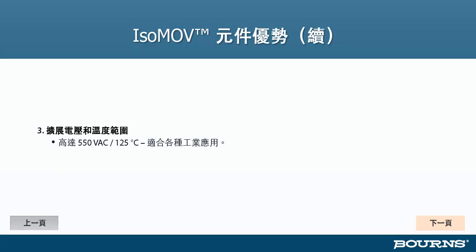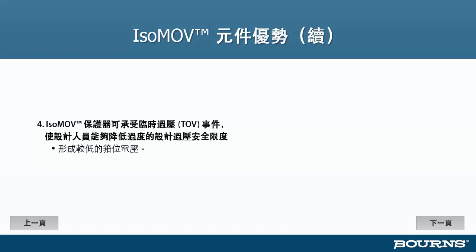Another feature of the new IsoMOV family of hybrid protectors is an extended voltage range. We're offering devices with a maximum continuous operating voltage of 550 VAC, which is suitable for 480 VAC line applications. This high voltage capability, coupled with the extended temperature range, make the IsoMOV protector especially well suited to industrial applications. Because the MOV and the GDT are rated to take the line voltage, we don't know exactly what the sharing is going to be between those two, because it's dependent on the aging characteristics of their histories and events. But what we do know is that the actual breakdown voltage of this device is going to be much higher than the breakdown voltage of either device separately, because they do share that voltage to some level.